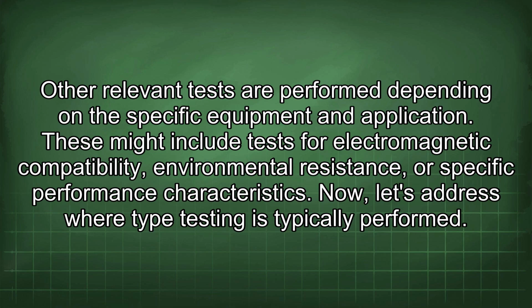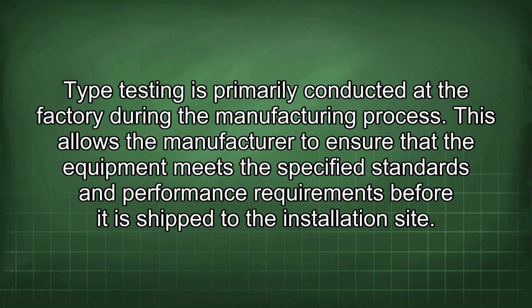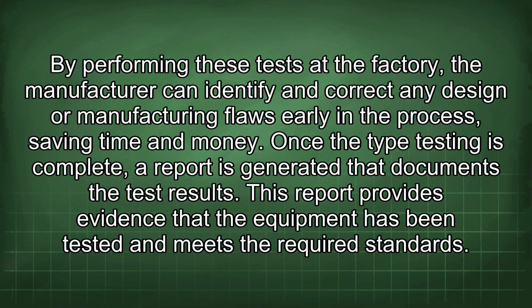Now, let's address where type testing is typically performed. Type testing is primarily conducted at the factory during the manufacturing process. This allows the manufacturer to ensure that the equipment meets the specified standards and performance requirements before it is shipped to the installation site. By performing these tests at the factory, the manufacturer can identify and correct any design or manufacturing flaws early in the process, saving time and money. Once the type testing is complete, a report is generated that documents the test results. This report provides evidence that the equipment has been tested and meets the required standards.